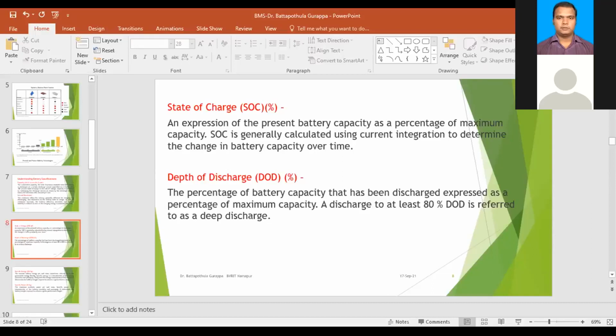Depth of discharge is similar, it should not be less than 20%. At least 80% of DOD means depth of discharge, meaning you need to maintain at least 20% of SOC. These two are vice versa, inversely proportional. 80% of DOD means at least you need to maintain 20% of SOC.